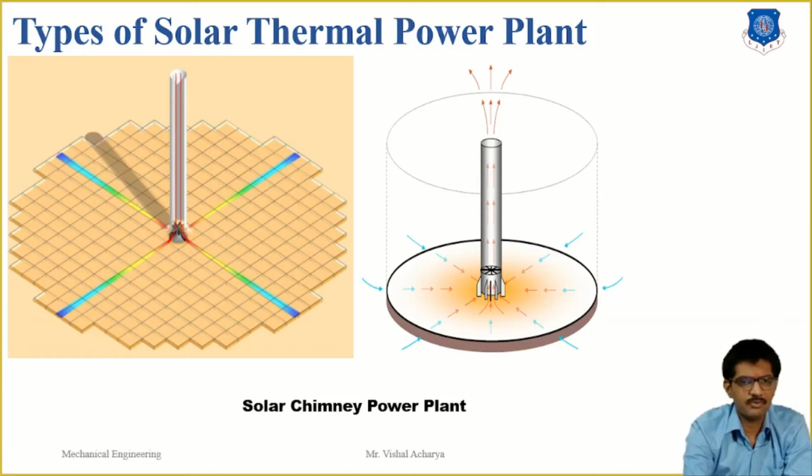Mechanical output in the form of rotational energy can be derived from the air current in the tower. Turbines in a solar updraft tower do not work with velocity staging like a free-running wind energy converter, but as a shrouded pressure-stage wind turbo generator, in which, similarly to a hydroelectric power station, static pressure is converted into rotational energy.